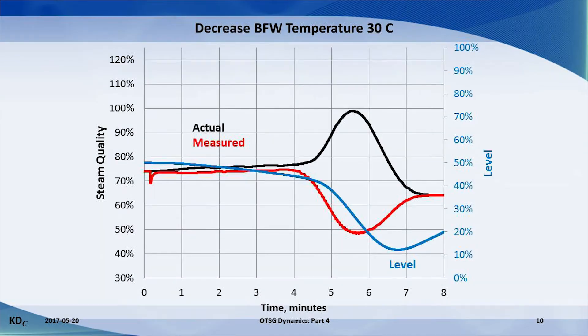The trend of the actual and measured steam quality shows the opposite patterns that were observed with the increase in boiler feed water temperature. The actual quality spikes high because there is insufficient water exiting the OTSG to keep it cool. A trip on superheat may occur. But the measured venturi quality dips low because of the low mass flow rate through the venturi, resulting in a low pressure drop.